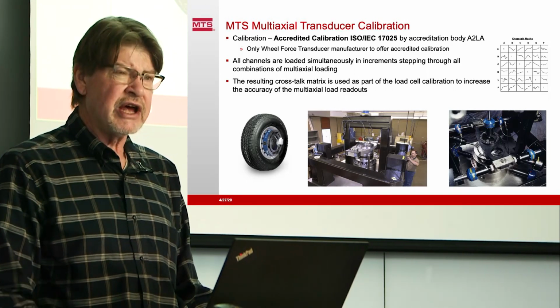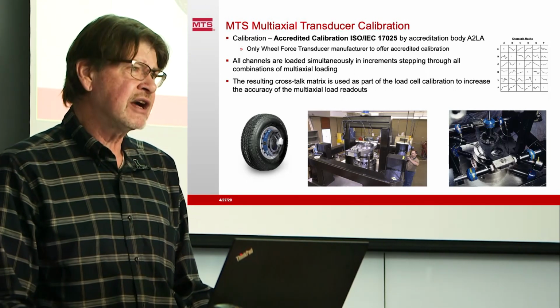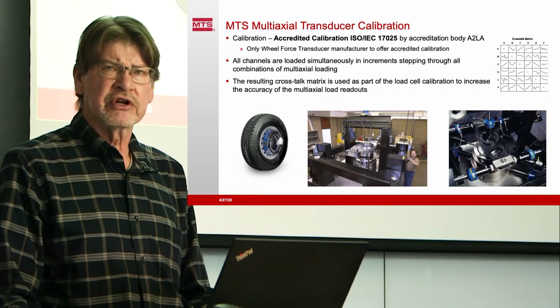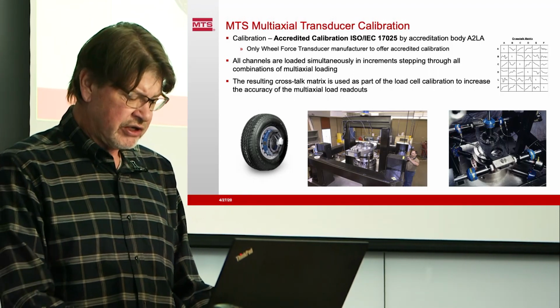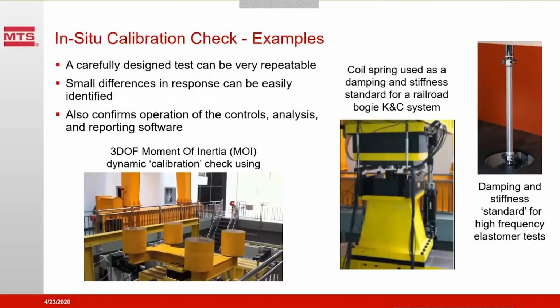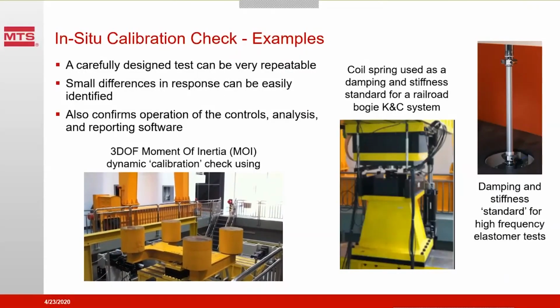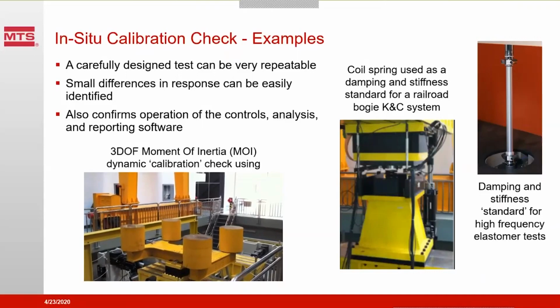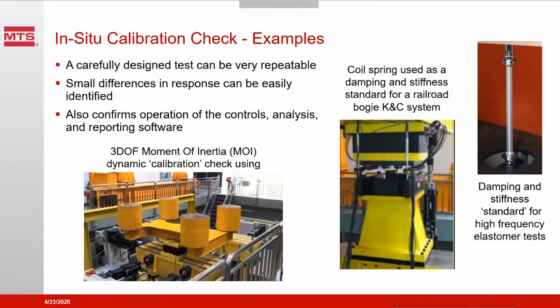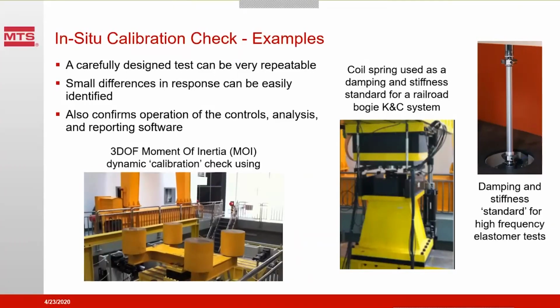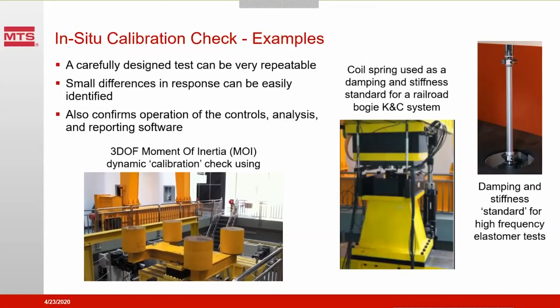We can then use that in a transducer conditioning box to calibrate the data and convert it so the output is as linear and decoupled as possible. In situ type calibration checks are demonstrated here. Maybe a moment of inertia check where we're swinging a known amount of weight in space at a known distance. We know it should have a certain amount of inertia.